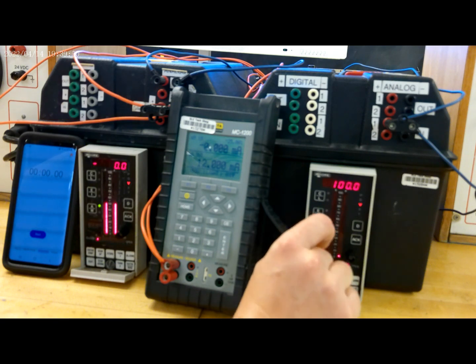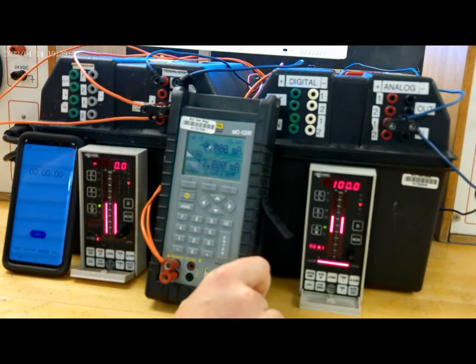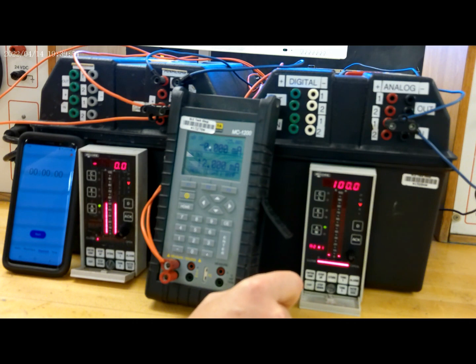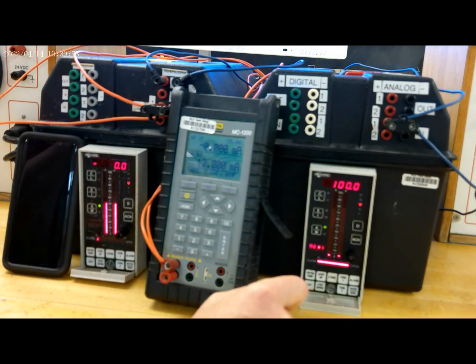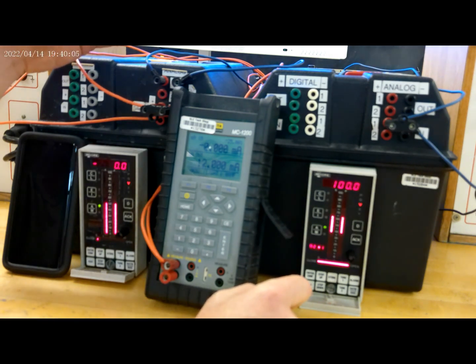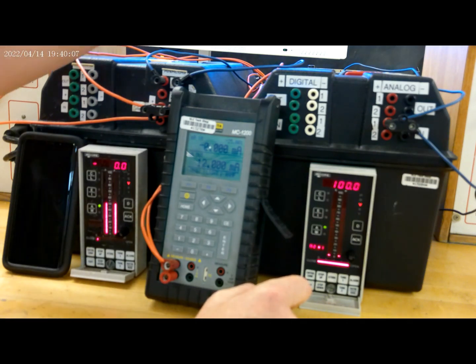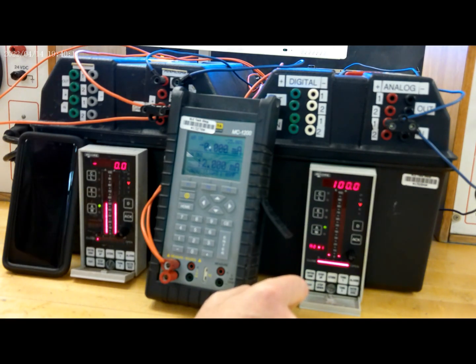The output is going to go from 100, instantaneously drop down to 91.84. Over the course of half a minute, it's going to go down to 71.84, and then as soon as the first controller goes above 100, the ramp rate will stop, and this controller will go back up to 80.